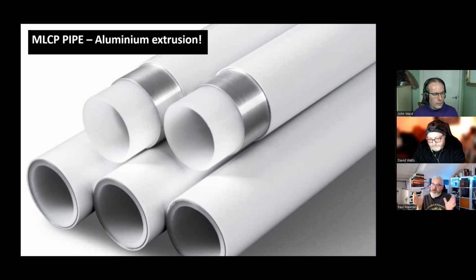But some of these pipes you can get are aluminium reinforced, which means there is a chance and a potential for voltage to travel down it. The reason I say this is because I work on railways. We've got 25,000 volt lines, and there is a chance that running insulated pipes, you could have a coupling effect. You can get transient voltages, etc. Depending on the magnitude of it, if a plumber installs it wrong, this could become a conductive pipe when we all think it's insulating.